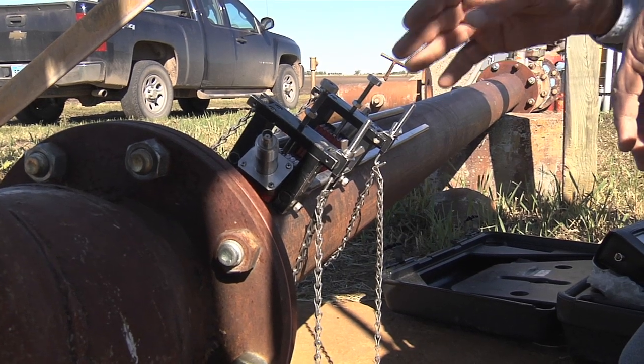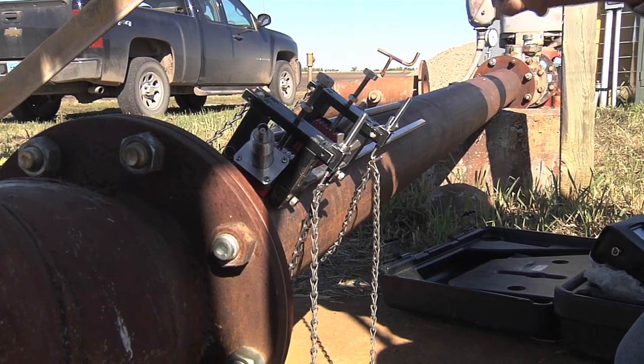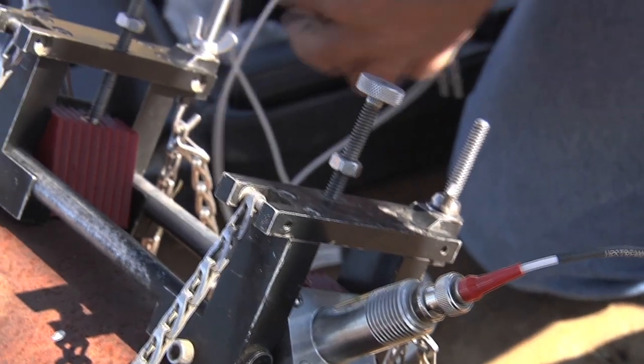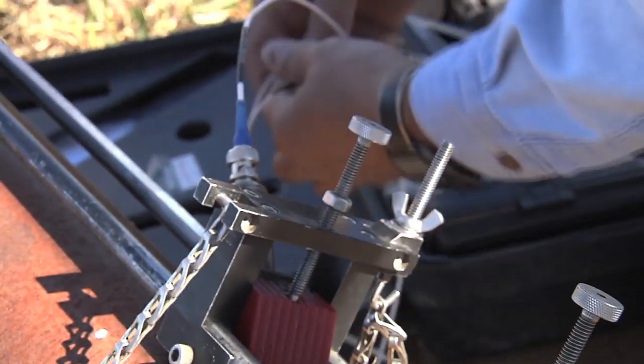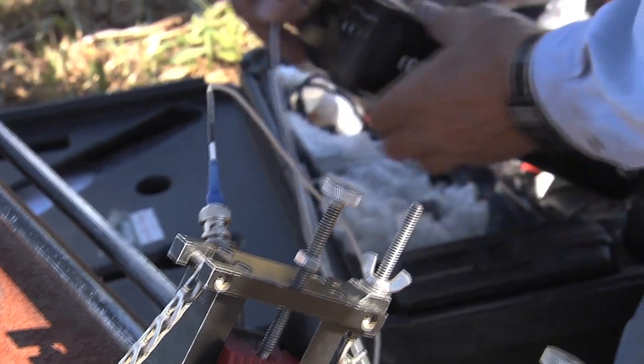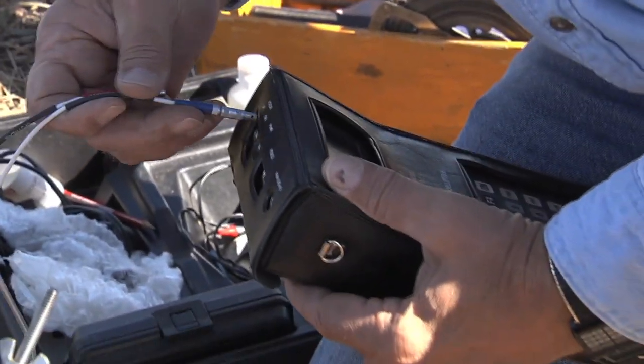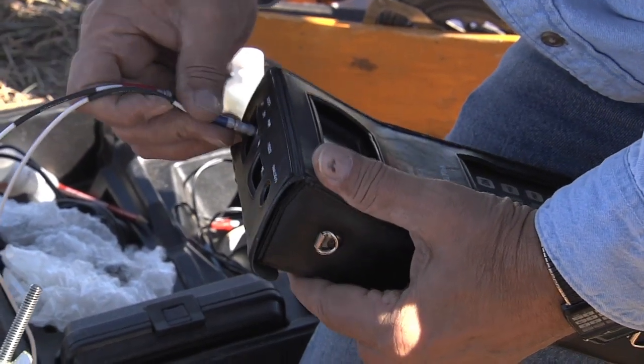It measures the time difference between the two, and then based on the time difference, and we know it's water, it then can calculate what the average velocity of water is in the pipe. And if I know the inside diameter of the pipe, which I can get from measuring it, then the processor here will calculate the flow rate for us and give us a good accurate estimate of what the flow rate actually is going out through this pivot when we turn it on.